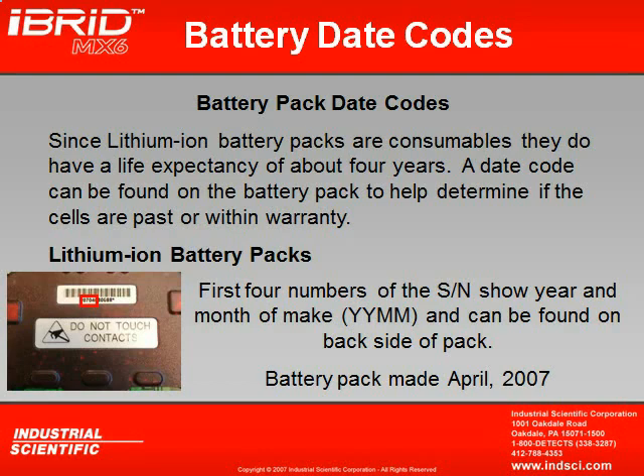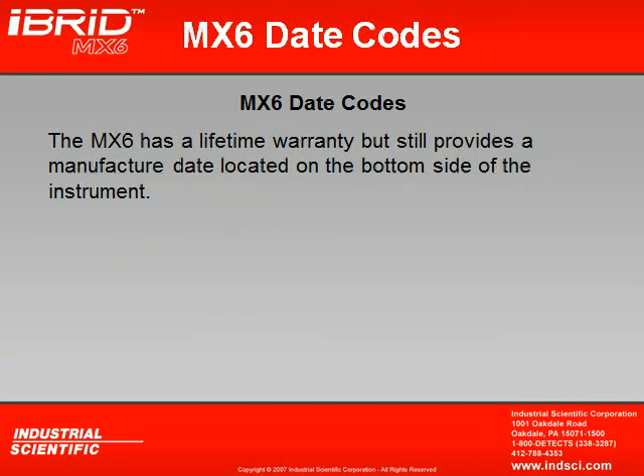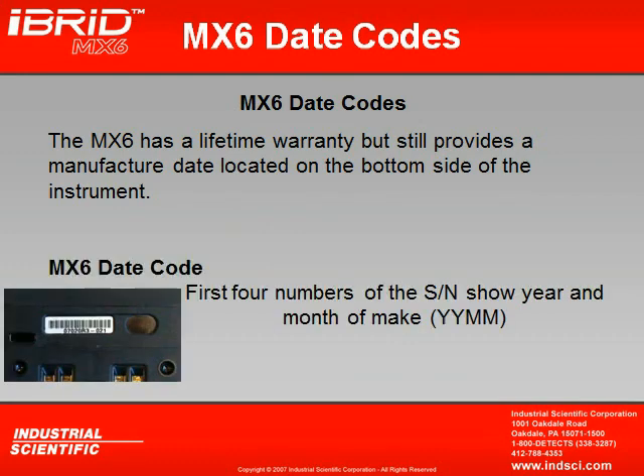Now the MX6 has a lifetime warranty on it, but still provides a manufacture date located on the bottom of the instrument if you need to see when the instrument was actually manufactured. So down where the charging contacts are, you'll see a barcode once again, and you read it the same way as the batteries, first four numbers, and it'll go year and month. First two numbers are the year, second two numbers are the month of when the instrument was made.